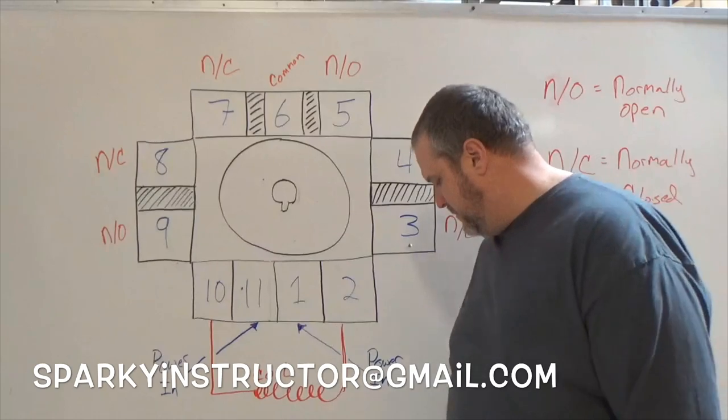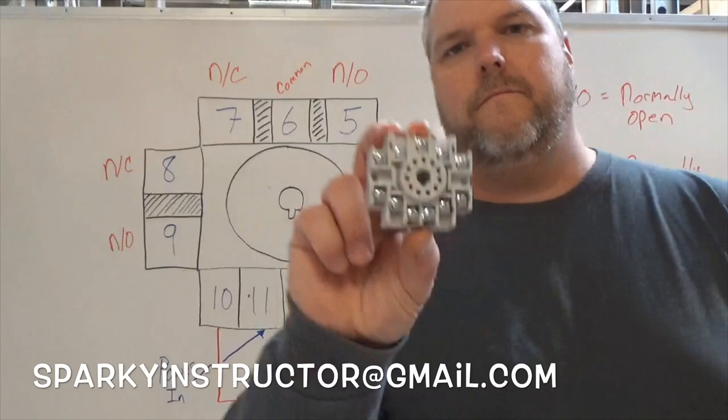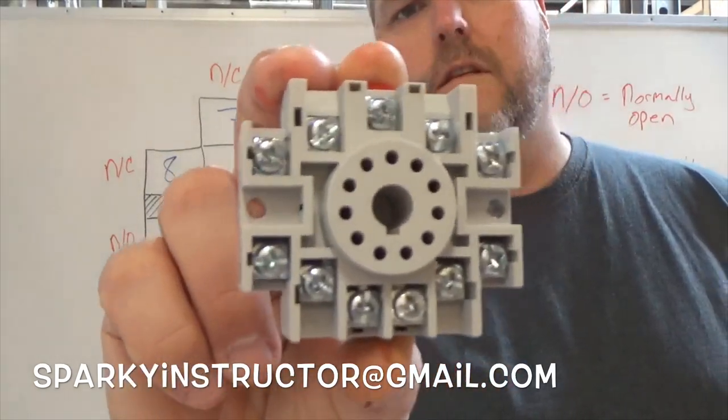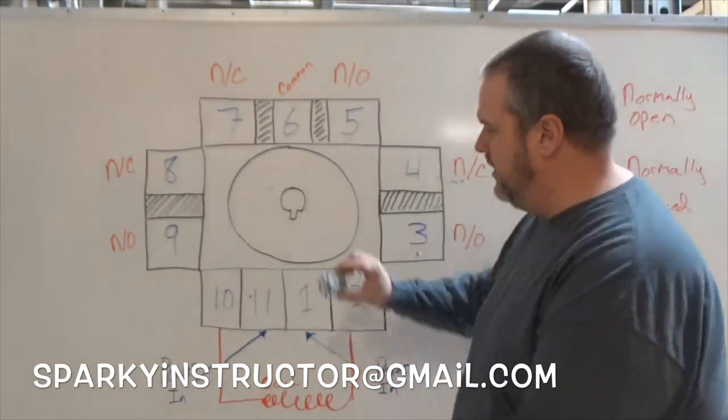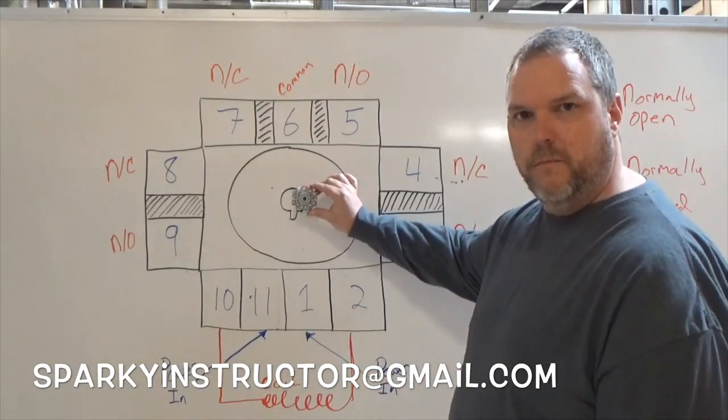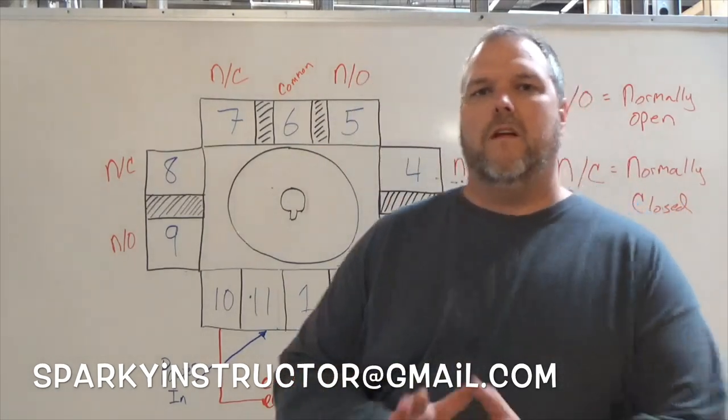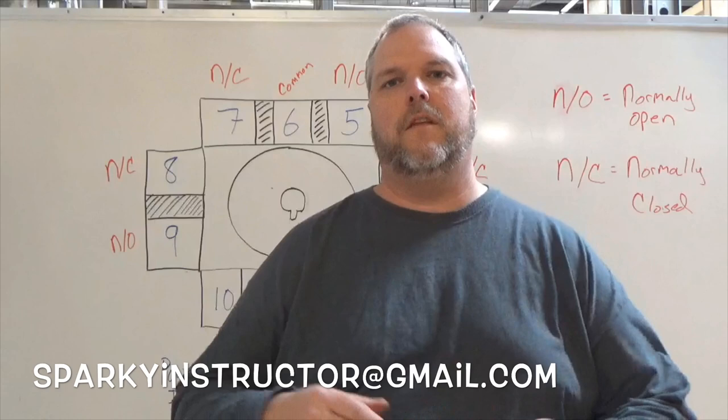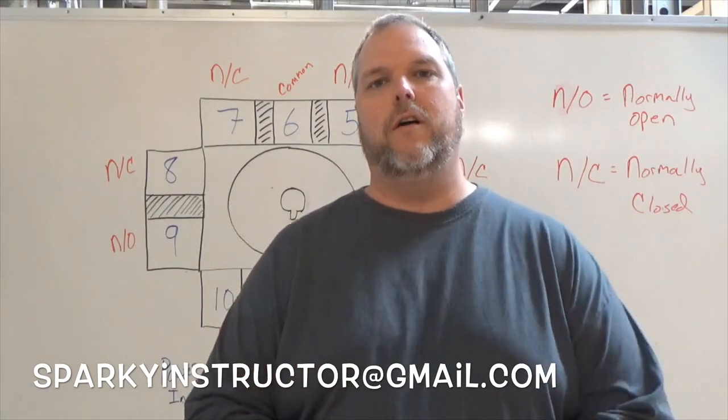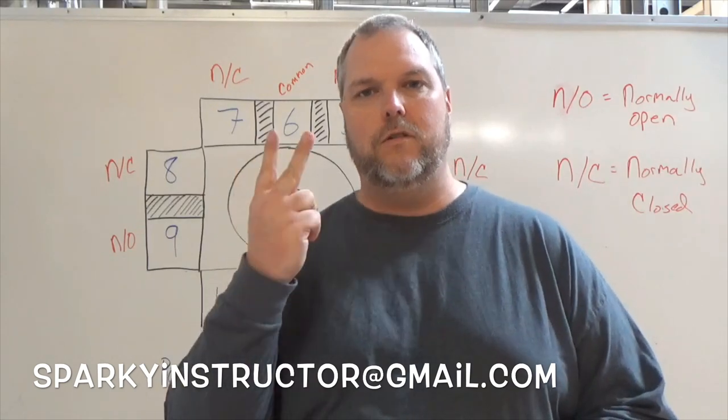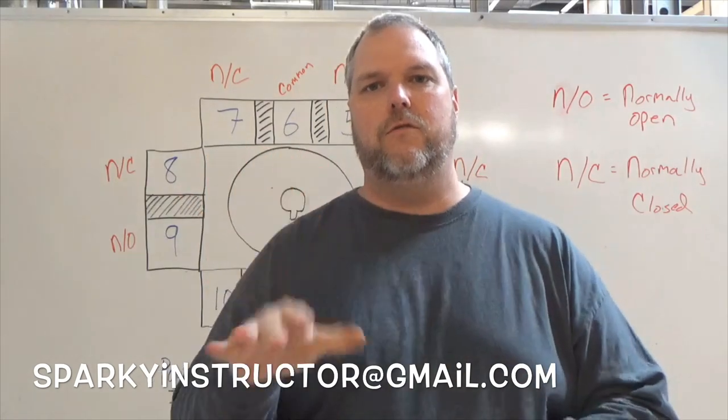So here, this is my base. You have an 11 pin base. What I did is I basically drew it a little bit bigger so that we can actually understand it. You can see what we're talking about. A couple of things you need to remember: your coil is the most important thing you need to remember. Your coil on an 11 pin is always going to be 2 and 10.